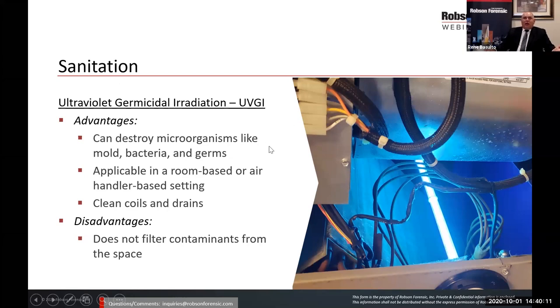It can destroy the microorganisms like mold, bacteria, and germs. You can apply it in a room-based air handling system. It'll clean the coils. It will keep the drains clean. The disadvantage is that it doesn't filter out contaminants from the space. But you're not relying on this to filter out the contaminants. You're using the filtration to filter out contaminants.